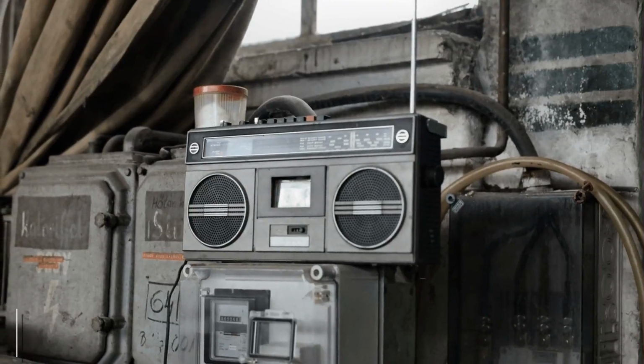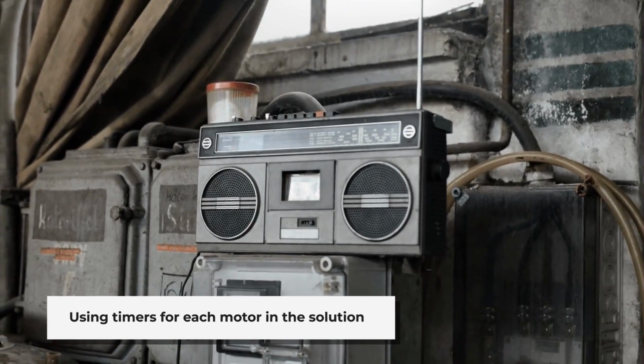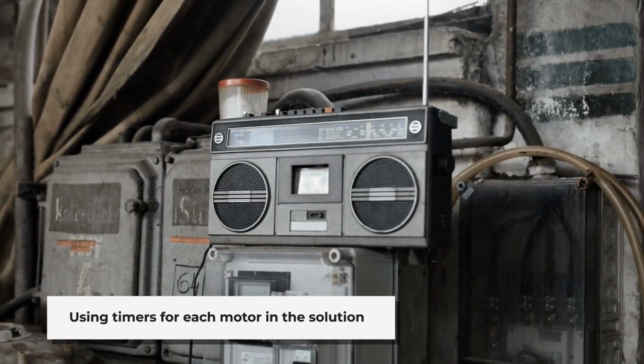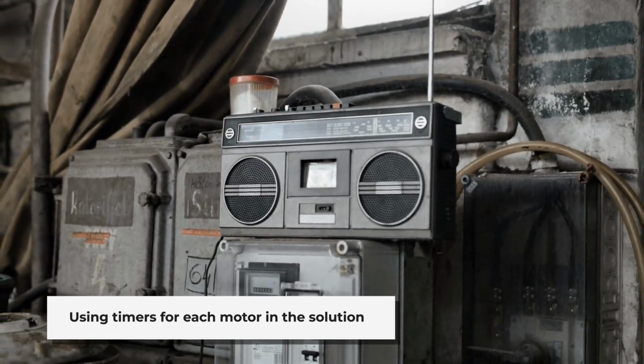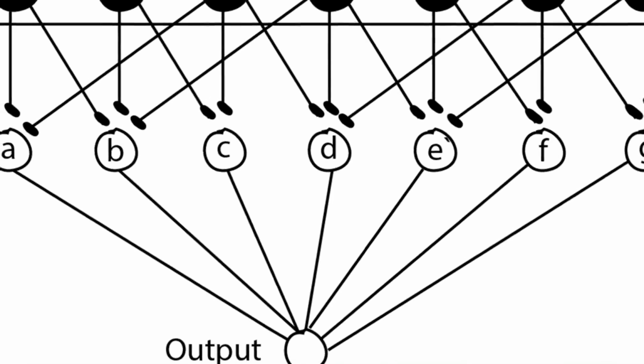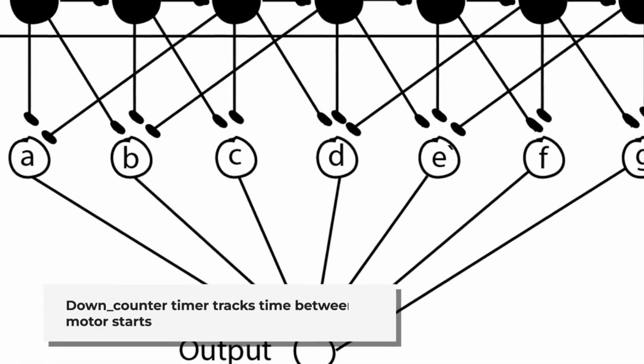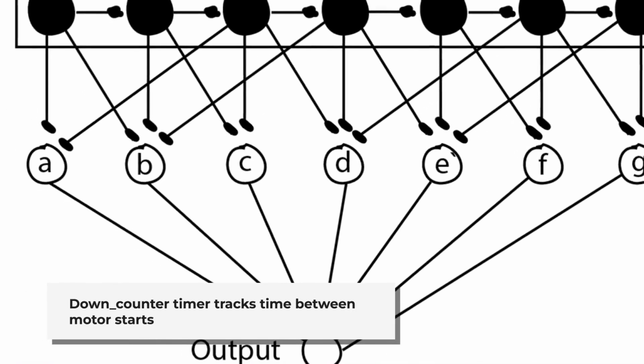Peter's solution involves using one timer for each motor, labeled as on delay 1, on delay 2, and so on, plus an additional down counter timer. This down counter doesn't control anything directly, but keeps track of the time between motor starts.